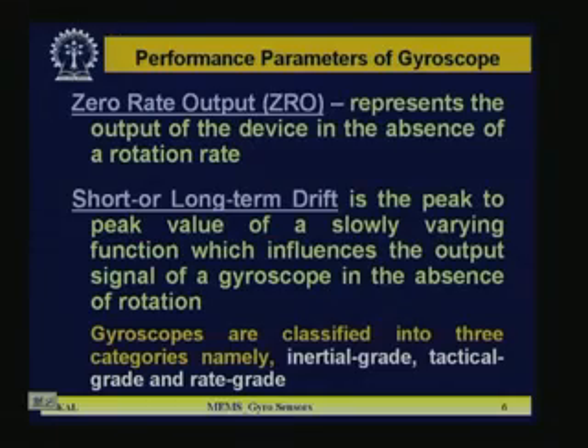Another important terminology is drift, short or long term drift. This is the peak to peak value of a slowly varying function which influences the output signal of a gyroscope in the absence of rotation. Short and long term drift mean the performance changes with time. Even the same device, if calibrated today and measured again after one or two years, you will find the calibration has changed. That is because of a slowly varying function influencing the output signal, responsible for long or short term drift. What that function is, you have to identify.